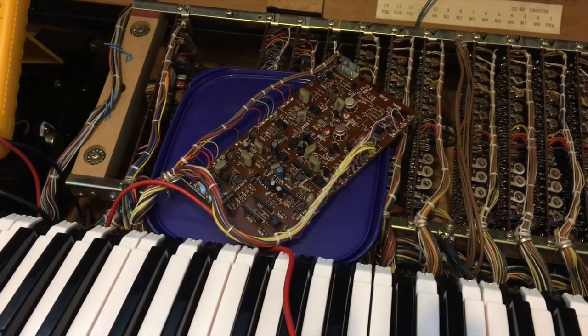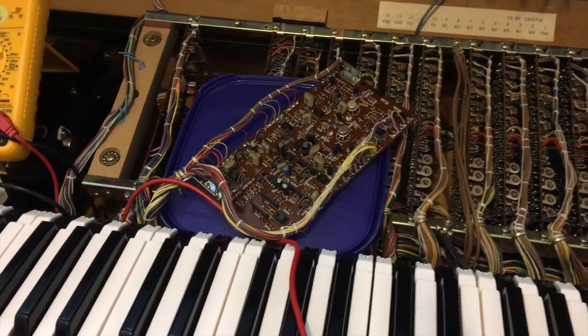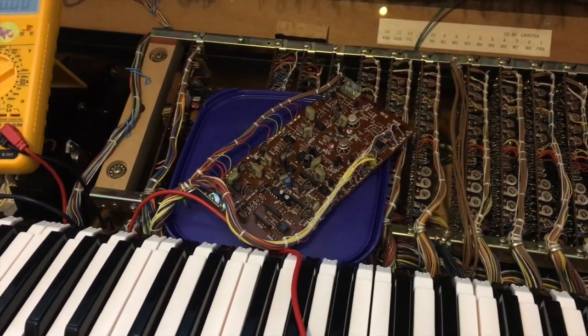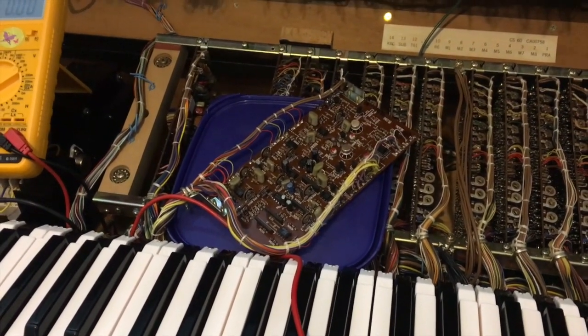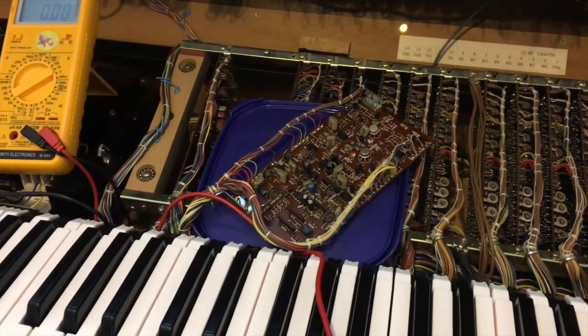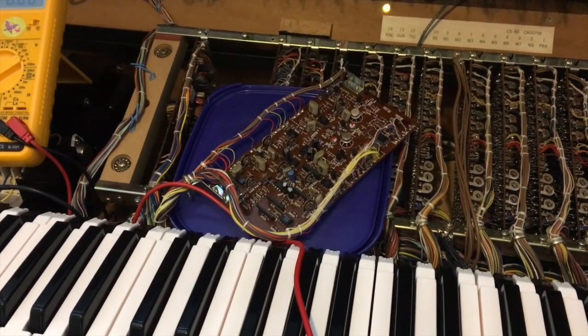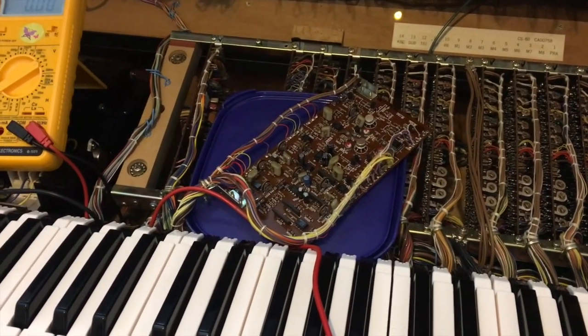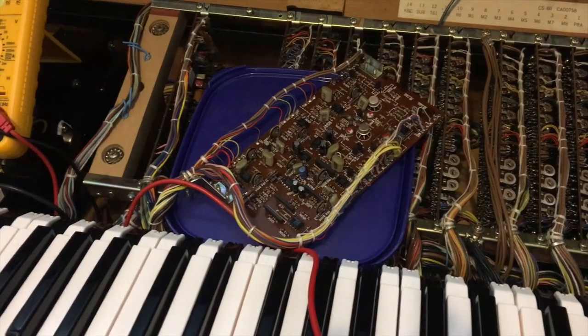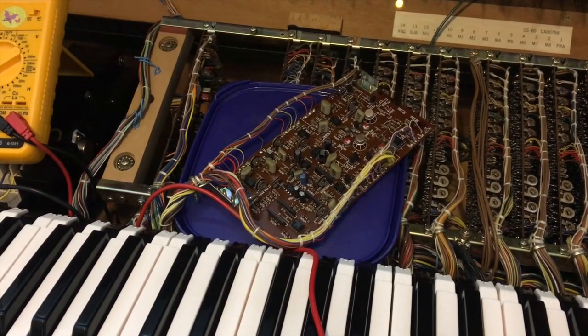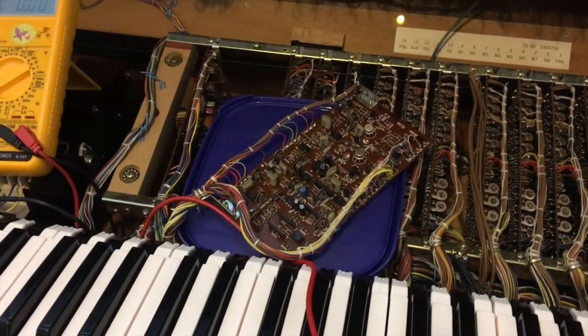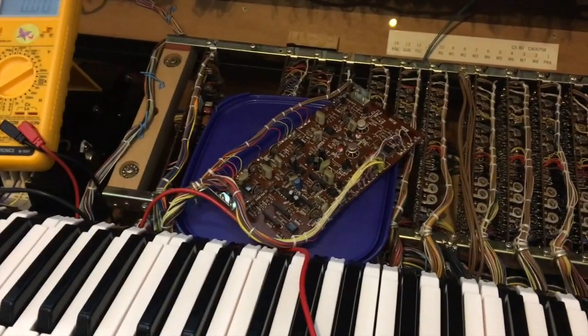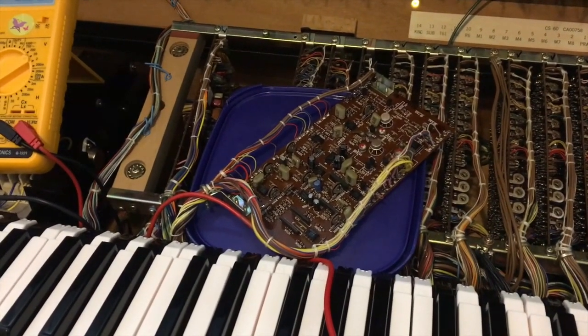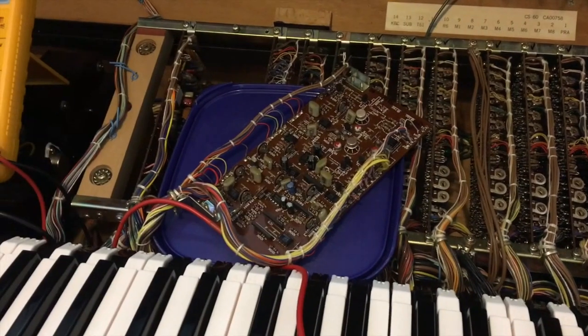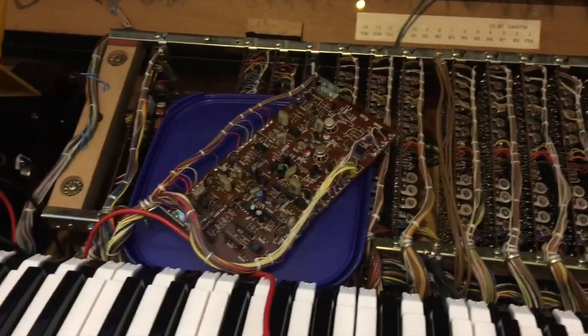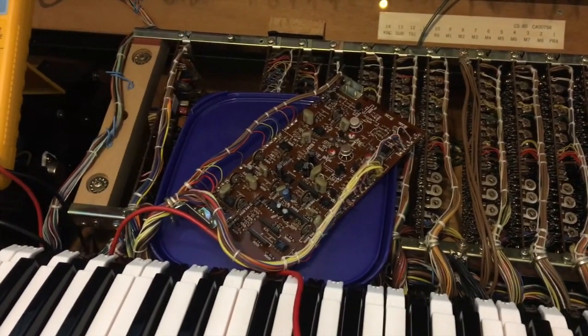Okay, so this subboard now presents us with our first calibration problem, and that is when a synth was successful, it was often produced for a longer period of time than the ones that weren't successful. And during that longer period of time, more engineering changes were made to improve things. And so quite often modifications were made to the circuit board and they didn't end up looking the same as when they started. And so the schematics and therefore sometimes the tuning procedures didn't really apply anymore. So the test points I need on this board for the first two tests aren't really there anymore. And also the circuit is a little bit different. So I'm going to do the first calibration a little bit differently to what the manual says, and I'll show you what we need to do first.